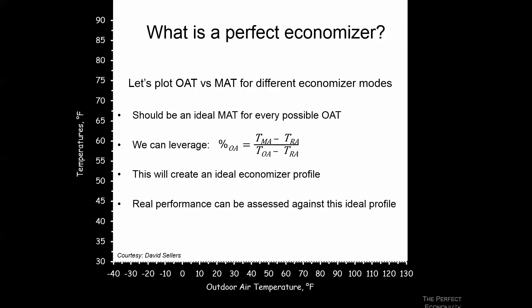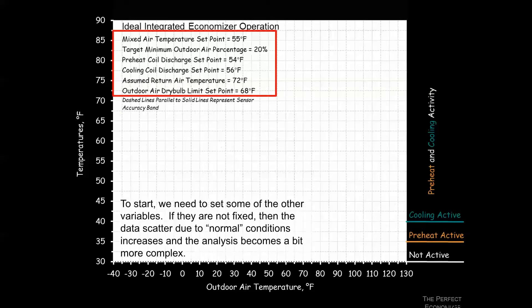Given these operating conditions — a 55-degree mixed air temperature set point, a minimum 20% outside air for ventilation, specific coil discharge set points, a constant return air of 72 degrees, and an economizer lockout at 68 degrees — we can now surmise what the economizer should be doing at any given outside air condition.